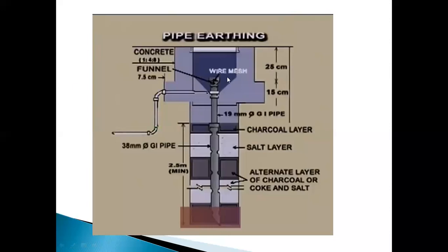In the summer season, the moisture in the soil decreases to a large extent, which will increase the earth resistance. So in order to have an effective earth, whenever needed, we need to pour 3 to 4 buckets of water through this funnel so that the earth around the pipe becomes somewhat moist.